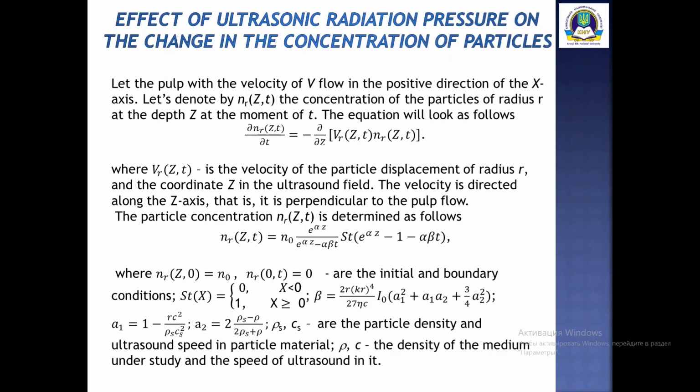The calculation of high energy ultrasound power, which allows the predicted displacement of particles of crushed ore at certain mass in the pulp flow, was carried out based on the result obtained from the study of ultrasonic power propagation. The concentration of the pulp solid phase in the measurement zone is determined using ultrasonic measurement, and the density of the particles using gamma radiation in the radiometric measuring chain.